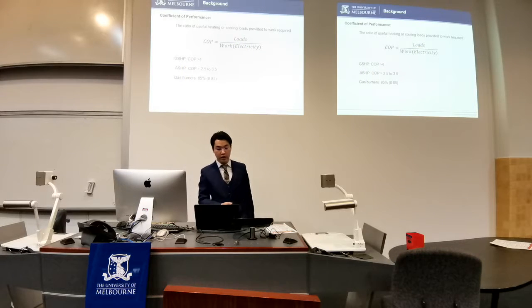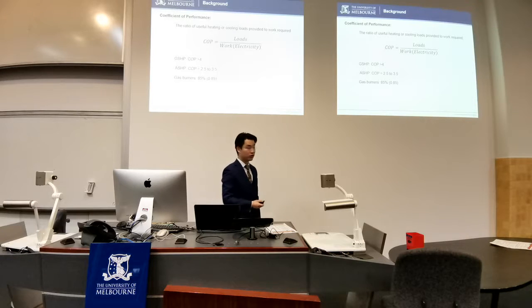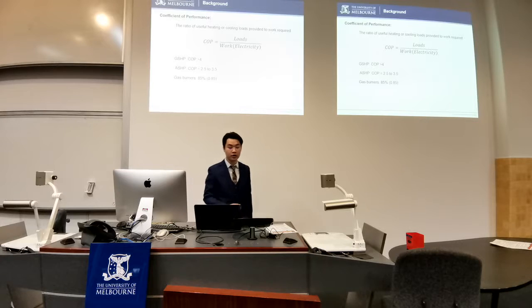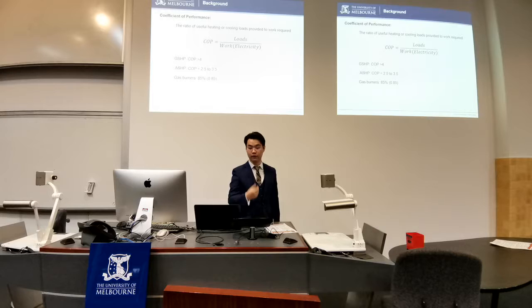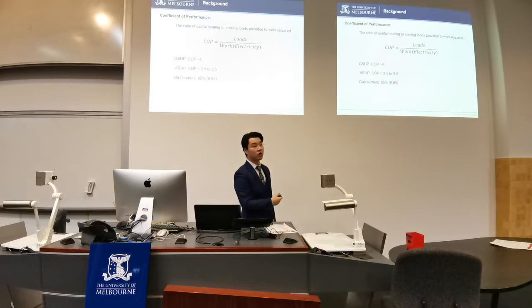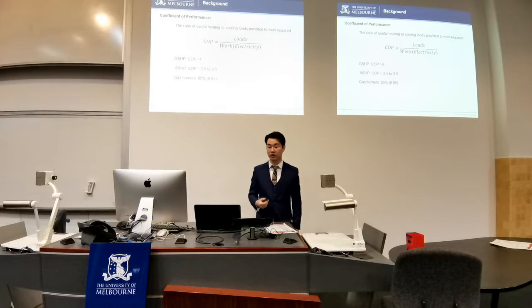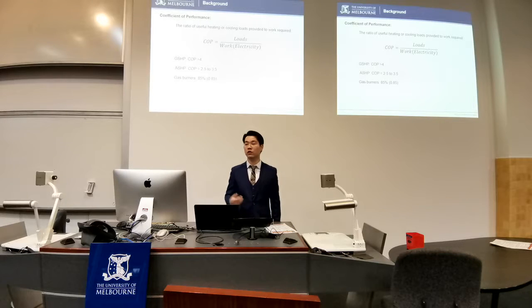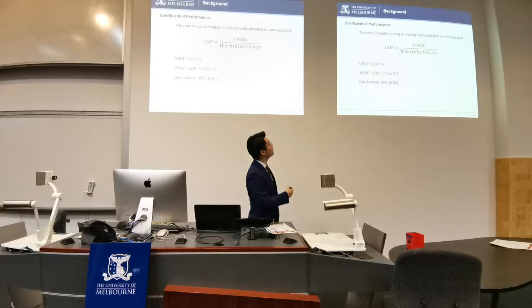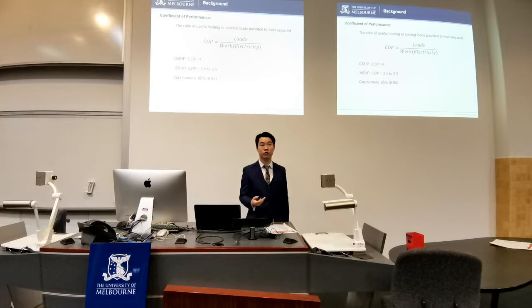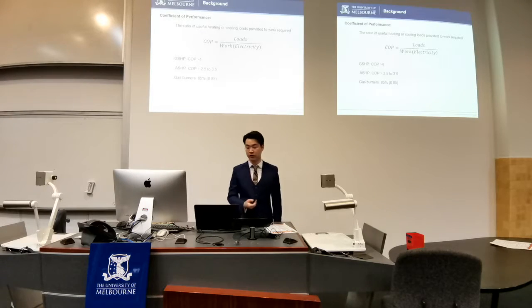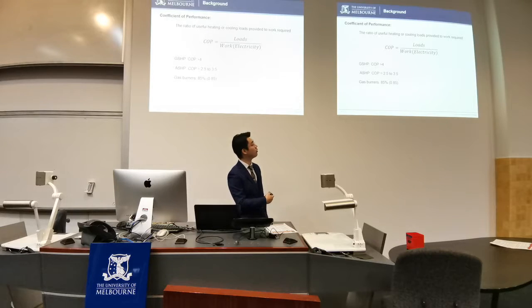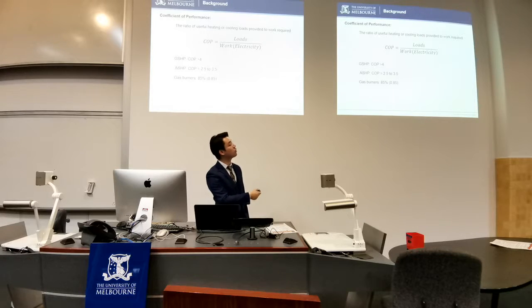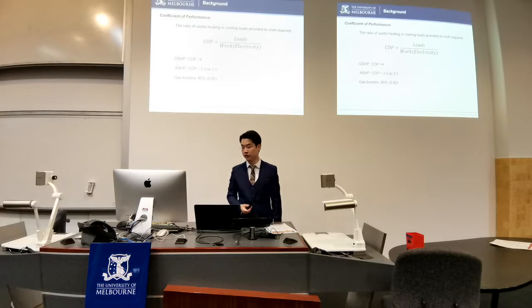For those of you who are not very familiar with HVAC systems, we typically use the coefficient of performance, COP, which is defined as the ratio of useful heating or cooling provided to the work required, as a measurement of the efficiency of the system. For example, for a well-designed ground source heat pump system, we can expect the COP to be larger than 4, which means that to provide over 4 kilowatt hours of heating or cooling demand, we only need to consume 1 kilowatt hour of electricity. As a comparison, air source heat pumps typically have a COP between 2.5 and 3.5, and gas burners normally only have an efficiency of 85%, which is equivalent to 0.85 COP. So you can see that the ground source heat pump is a state-of-the-art technology with very high efficiency.